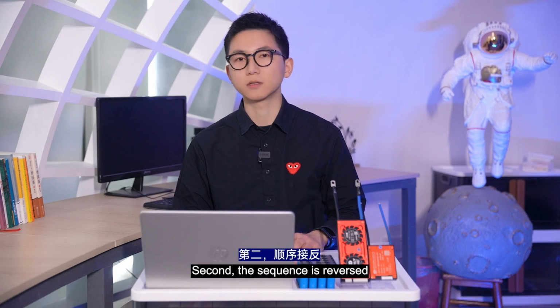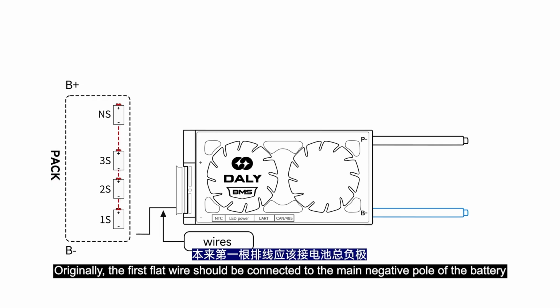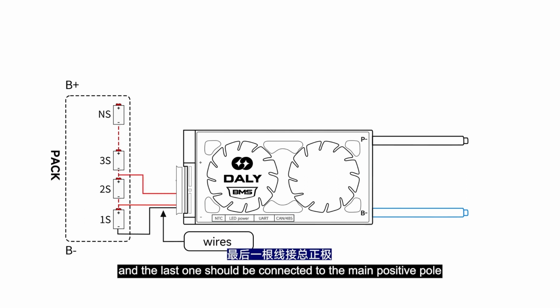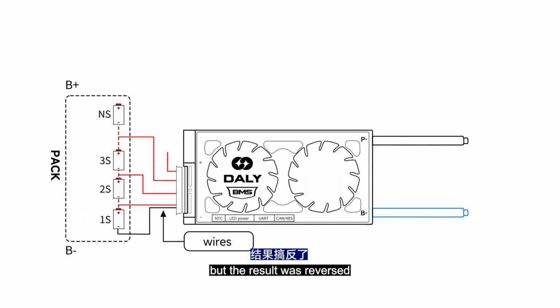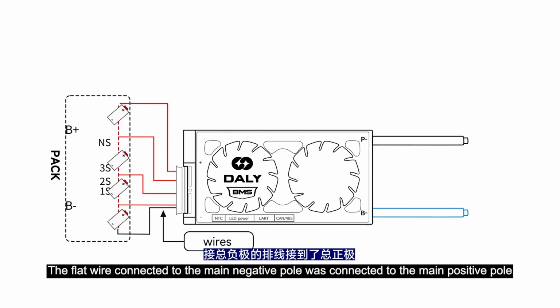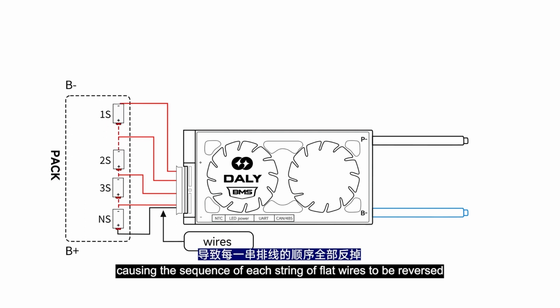Second, the sequence is reversed. Originally, the first wire should be connected to the main negative pole of the battery, and the last one should be connected to the main positive pole. But the result was reversed: the wire connected to the main negative pole was connected to the main positive pole, causing the sequence of each string of wires to be reversed.